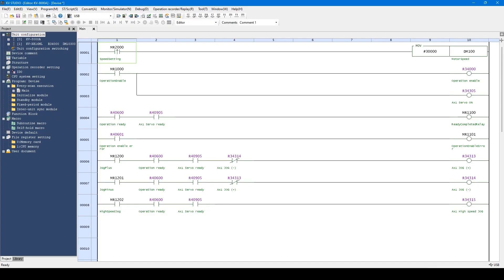Let me explain about devices. With KV, you can program by using a device as well as using a variable. Device means a memory provided to KV as a default. Unlike variables, you can use the device without defining a name and a data type. With KV, functions allocated to the unit, such as servo on and servo ready, can be allocated to a device. The device consists of the bit device to store on-off data, the word device to store numeral values, the timer, and the counter.